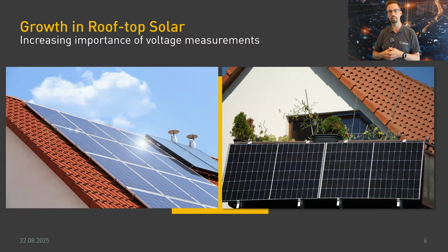So where this issue presents is down at the end of the line, not at the beginning where we tend to take our measurements in the substation. It's down at the last house or the last distribution cabinet where you're going to see the extent of this voltage rise. And that's the main reason why we've wanted to introduce this product, so our network operators can see what is the extent of that voltage increase on the line - I need to be able to measure it as far out into the network as possible.